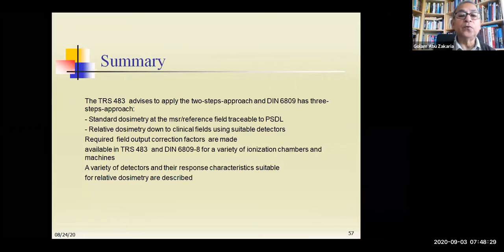The TRS 483 advises to apply this 2-step approach. The DIN 6809 has a 3-step approach. Standard dosimetry at the MSR or reference field, traceable to a primary laboratory. Relative dosimetry down to the clinical field using suitable dosimeters.